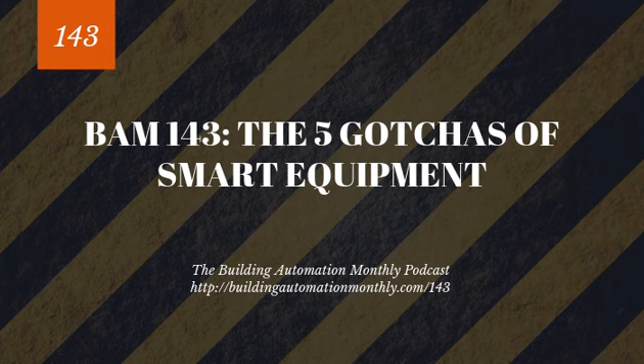And by being aware of these dependent systems, that then lets you know if you can do what is in the sequence. So for example, if you see that there's a trim and response for speed control of the VFD on the supply side of this VAV air handler, yet there is no way to control that in the system, meaning that you can look at all the VAV box commands and or temperature, or however you're doing trim and response. You can look at that, and then you can do a calculation in your supervisory device, and you've got the plus and minus for your trim and response algorithm, but you can't send that to the packaged unit because that packaged unit does not have a way for you to adjust the differential pressure set point for the supply fan control. Then hey, the sequence is great, but you can't do it. That's what I mean by understanding dependent systems, both upstream and downstream.